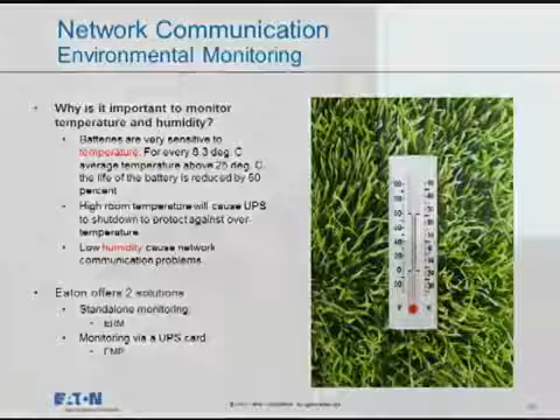We went one step further and created an environmental monitoring probe, which brings in temperature and humidity, as well as two additional relays, ties it into the card itself, and uses that card's communications to send it out, piggybacking on the communications of the enterprise.